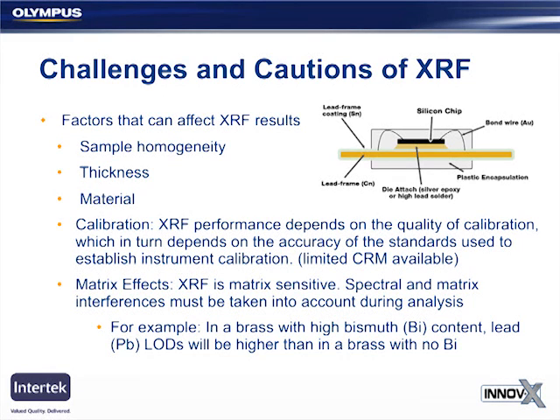Sample thickness can have some effect on your measurement, mainly by raising detection limits when samples are very thin. The IEC document that I mentioned earlier has some recommendations for minimum sample thickness when testing by XRF. For plastic materials, it gives a recommendation of 5 millimeters minimum thickness, so you don't want to go any thinner than that. If you do, be aware that your detection limits may be higher.